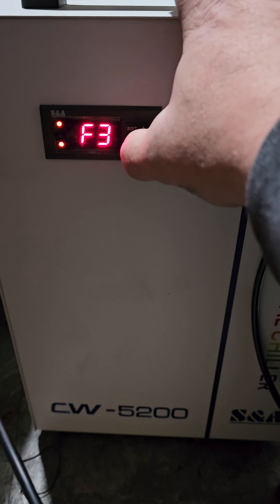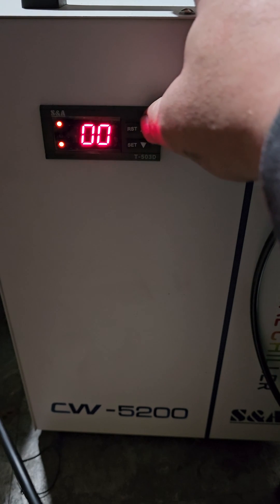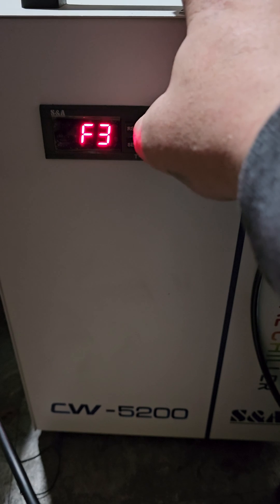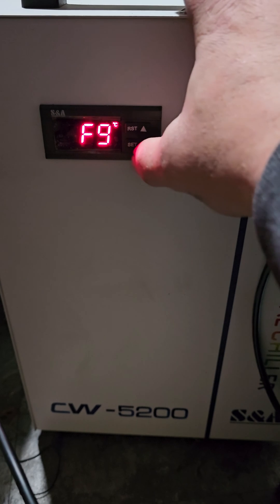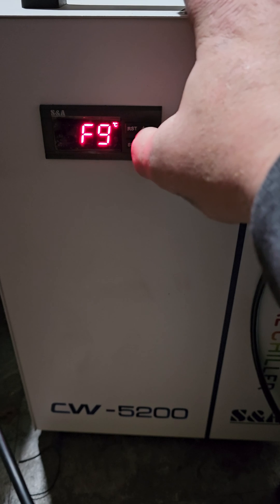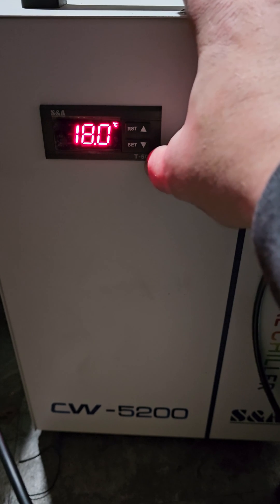F3 is where you turn on your constant mode. Hit Set — you want it set to zero. Once you've got it set to zero, hit Set. Now we're going to go up to F9, hit Set. I've got this set to 18 degrees Celsius as my low temp. Hit Set and then we're going to go back up to F0.